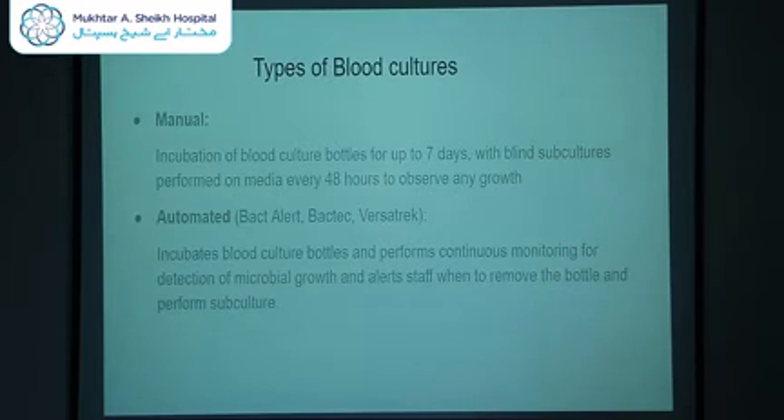The next is automated blood culture, which we have recently acquired. This can be conducted on machines like Bact Alert, Bactec, or Versatrek. It incubates the blood culture bottles and performs continuous monitoring every 10 minutes for detection of microbial growth, alerting staff when to remove the bottle for subculture.